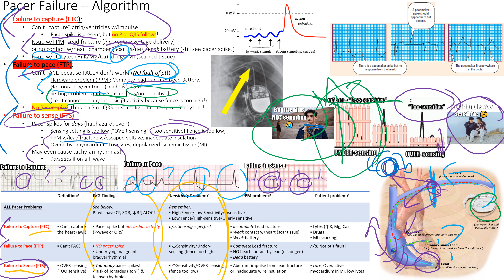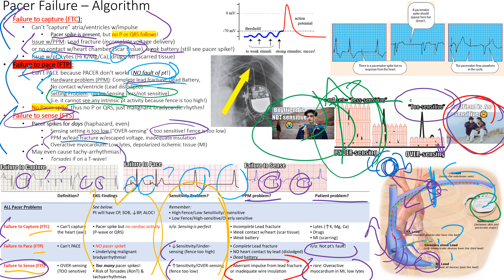Okay, so what are the sensitivity problems? We talked about that in detail. And then is it a pacemaker problem or is it a patient problem? In failure to pace, it's not a patient's problem. It's just that the pacemaker has failed, or a lead has completely fractured, or there's something wrong, or it's been dislodged, right? Whereas failure to sense is usually not a patient problem. It's rare. It's usually a sensitivity issue. We've cranked the sensitivity up way too high. Our boyfriend is way too sensitive, and they're responding to every single P wave artifact or anything that's being thrown off, and is throwing pacer spikes out there willy-nilly.